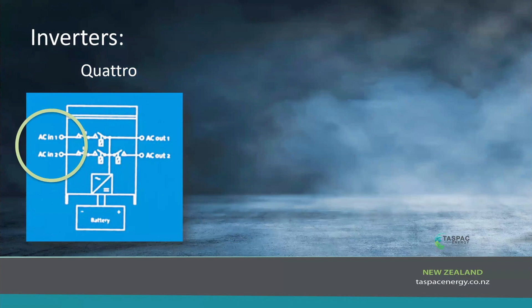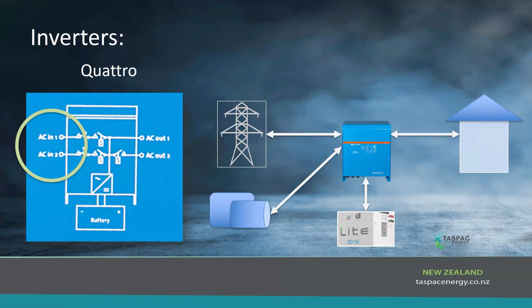The other thing with an off-grid system is if you've got two AC inputs, you could wire one to the main generator, and you could have one as a plug that you could plug a normal 10 amp generator into if the main generator is away for servicing or simply just breaks down, because generators do break down. Oh yeah, I was just explaining that. I should have had that diagram up. There's the example of the Quattro running two AC inputs. Okay, so we can move along there.